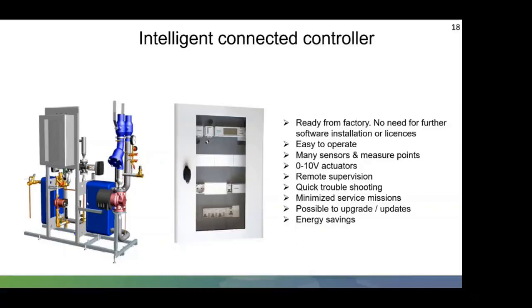Highly efficient substations usually have correctly placed sensors connected to the controls, which enable quick and clear monitoring. So looking at the flow and return temperatures, looking at the differential pressure control. Is there a blockage at the filter? Is there a blockage at the plate? Has a pump gone down? Is the pump working properly? Are the inverters on a pump working properly? Are they on a fixed speed or on a variable speed? So again, all this needs to be taken into consideration when you're designing a control panel, so everything works together and gives the information back to the end user or the building controller to make sure that they understand.